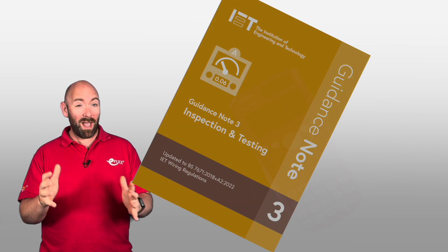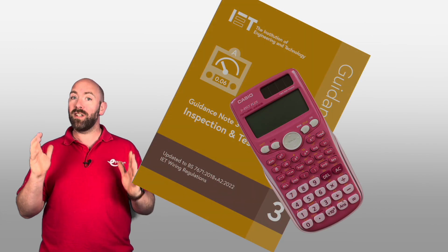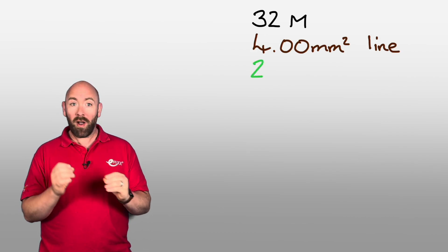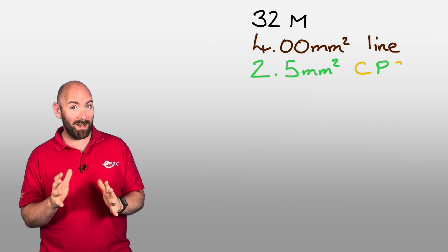So let's start with how we can calculate our expected R1 plus R2 values of an electrical circuit. You will need Guidance Note 3, a calculator, and something to write on. Our circuit is 32 metres in length with a 4 millimetre squared line conductor and a 2.5 millimetre squared CPC.